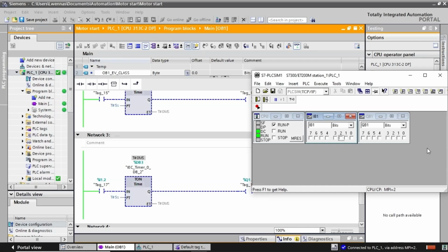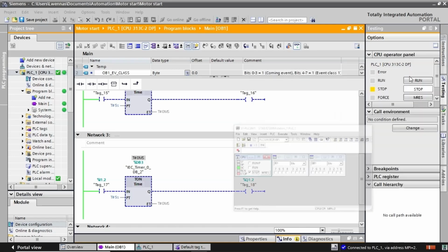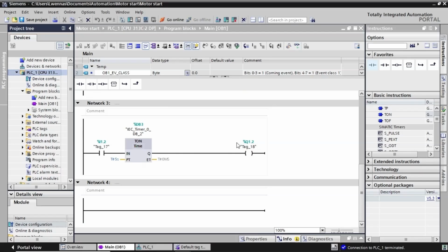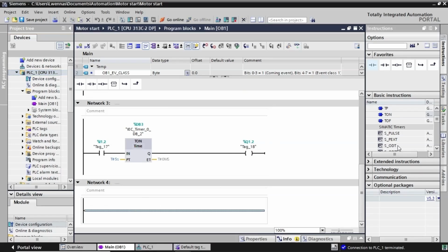Hopefully, you got the whole thing about timers. By the way, the lesson aims at providing a broad idea about timers. To have a full grasp of them, we need to put them in practical examples. Before we move to the next timer, it's worth pointing out that these timers are reset from the input signal. In case it is a pulse timer, all we need is generating another pulse to reactivate the timer. If it is an extended signal timer, we need first to deactivate the input and then generate another signal to reactivate the timer.